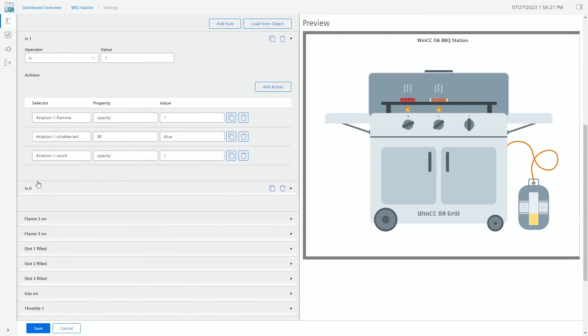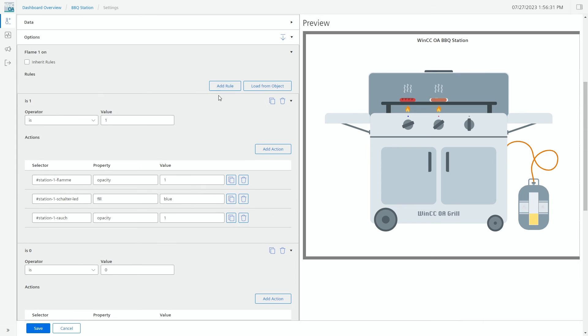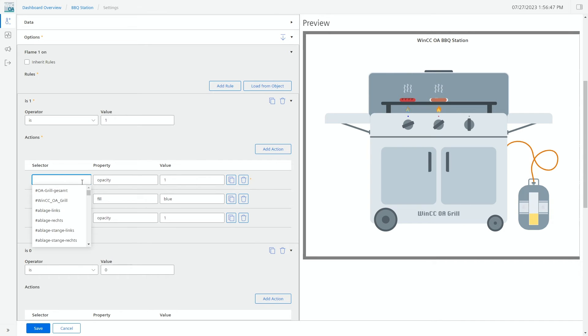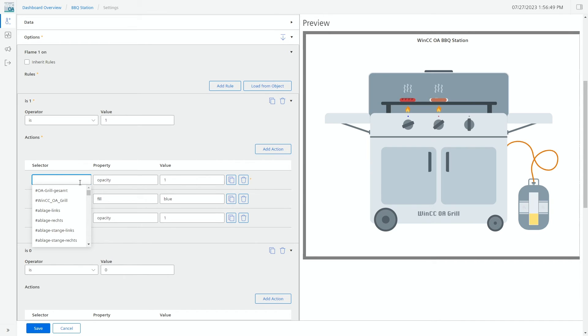These are all our input signals, for example flame one on, and there is the rule for the operator being true or the operator being false. And that is also the wizard how you would create those rules. That means you can add multiple actions. You can also add additional rules. Boolean is just true or false, I only need the two states defined, but it can have a lot of actions and different things set to the different properties.